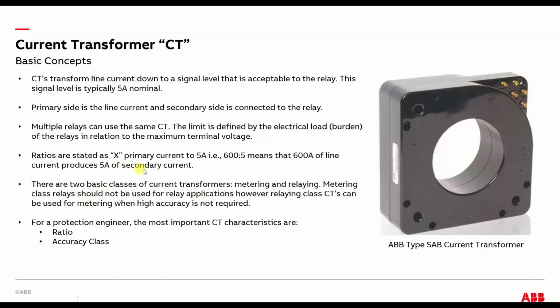So that was a little bit contrived, but let's see if I can clean up a little bit. Yeah, back to the ratio, the first part of the ratio, like for example the 600 here, means that 600 amps of line current will produce a 5 amp secondary current in the CT. Oh, here's an interesting note. There's two basic classes of current transformers. One's for metering, so there's a metering class, and then there's a relaying class. Don't use metering class CTs for protective relaying applications.